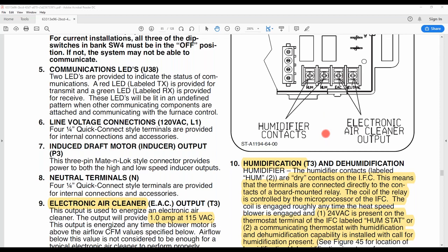Now the humidifier terminals. One important thing to note: those are dry contact terminals, meaning they do not supply voltage out of them from the control board. So these terminals here, after a period of time and after we go through some things, it actually closes contacts between them. These will show continuity between them when we have a call for humidity and certain demands are met. And I'll get into the wiring of that here pretty soon.